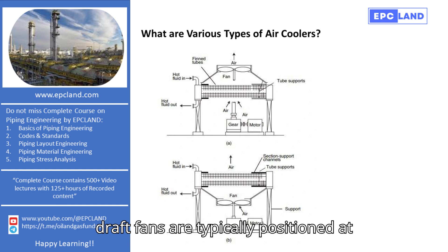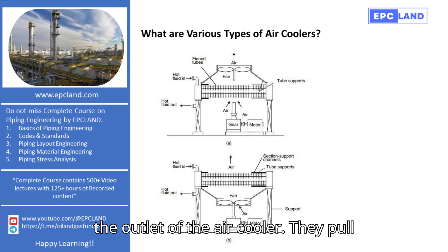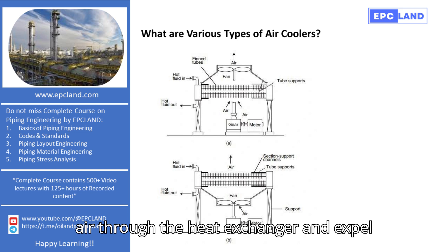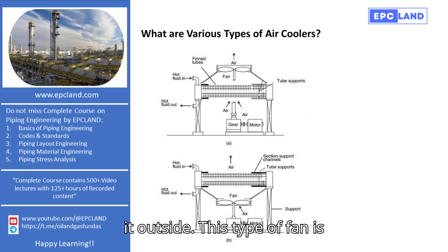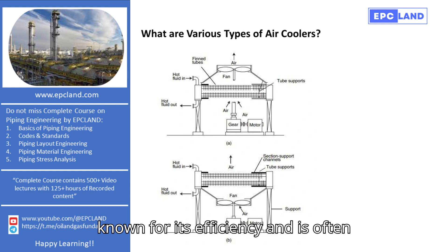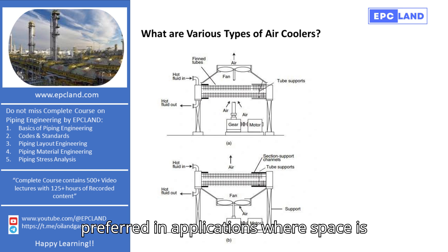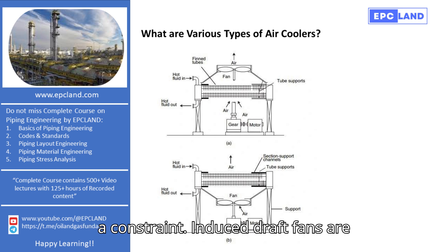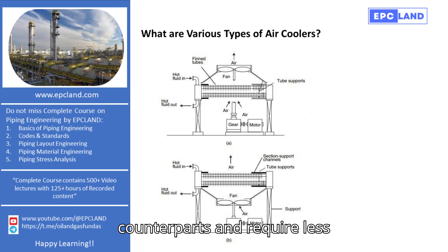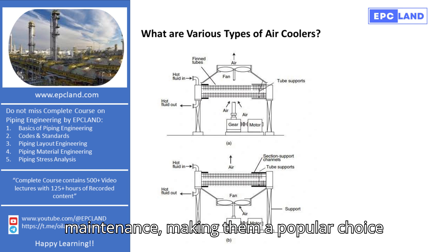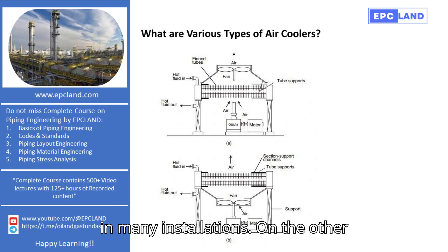Induced draft fans are typically positioned at the outlet of the air cooler. They pull air through the heat exchanger and expel it outside. This type of fan is known for its efficiency and is often preferred in applications where space is a constraint. Induced draft fans are quieter compared to their forced draft counterparts and require less maintenance, making them a popular choice in many installations.